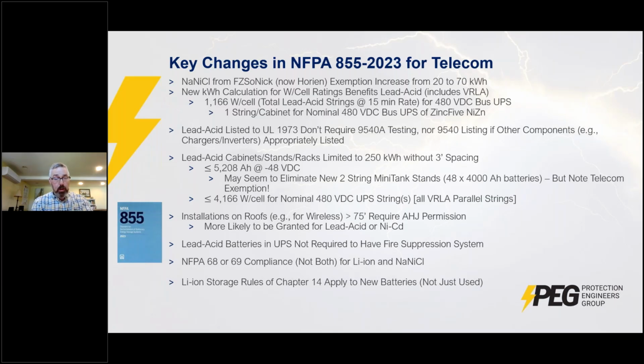It's really just a lithium concern. I mean, lead acid batteries don't tend to burn in that fashion as we typically use them, or NiCad, or lots of other technologies. So they've included an exemption for lead acid, that if the lead acid battery is listed to 1973, you can have a stack or a string up to 250 kilowatt hours before you have to separate them by 3 feet. For telecom specific applications, for 48 volt and for everything that's good about telecom, they've actually gone even broader.